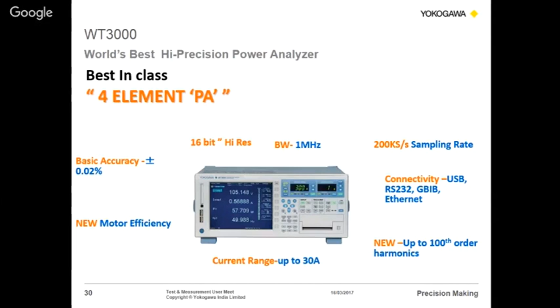That means for motor efficiency, it can take the input of the speed and torque signal, so it can calculate the mechanical power. Electrical power is the input to the motor, and the output of the motor is in terms of speed and torque, so it calculates the mechanical power and gives you the efficiency of a motor. Output by input, mechanical power divided by electrical power, gives the efficiency. It has all the latest connectivity like USB, RS232, GPIB and Ethernet.